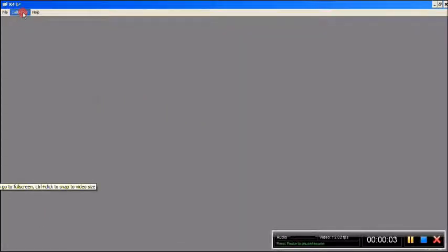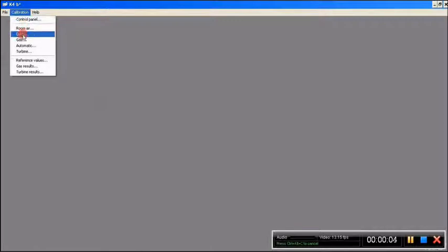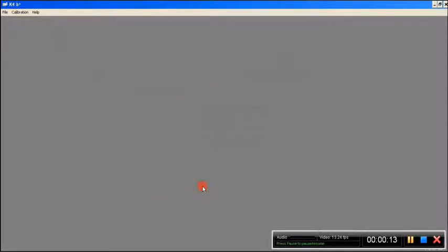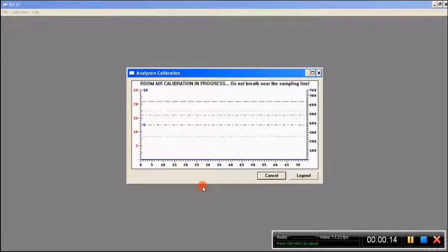This is the last calibration video. You're going to do the delay calibration. So you're going to go ahead and just select delay, read all your notes, click OK. Afterwards, you're going to be prompted with a graph. It's going to say room air calibration in progress, just like it did in the last three calibrations you did. Don't breathe near the sampling line.